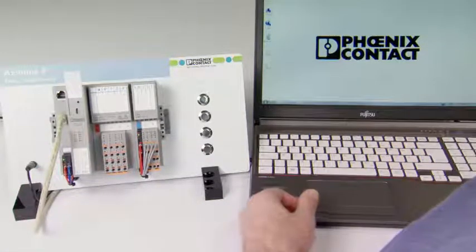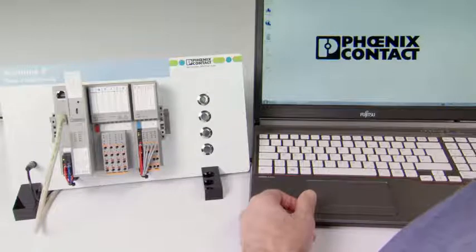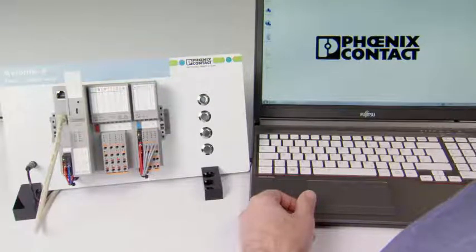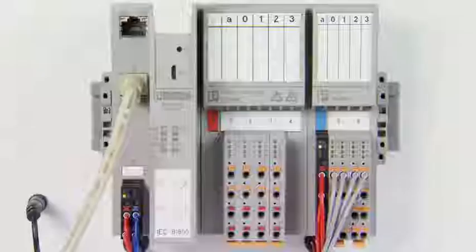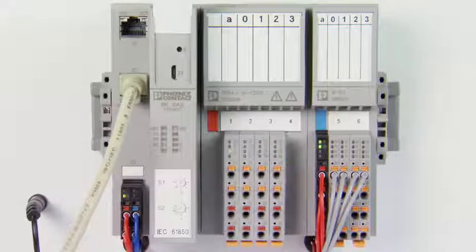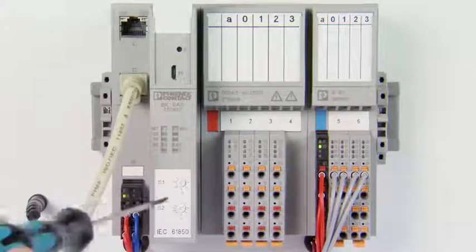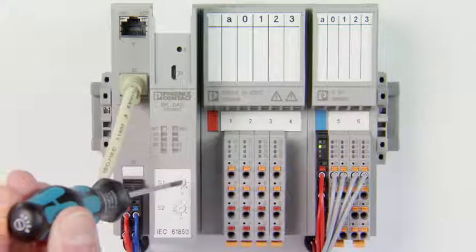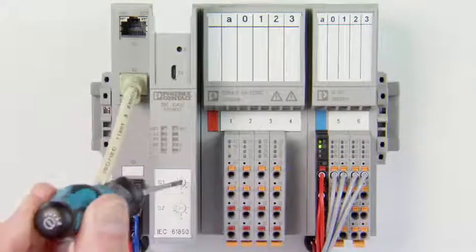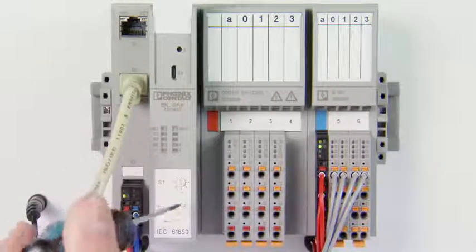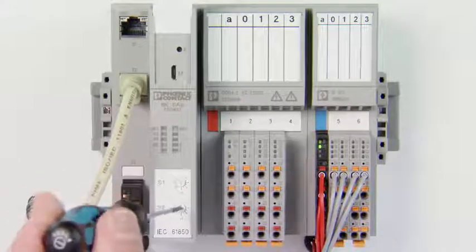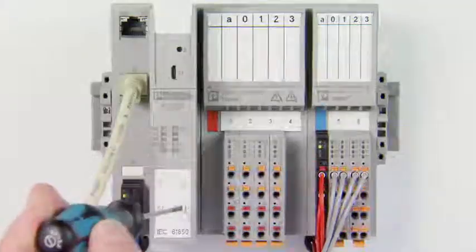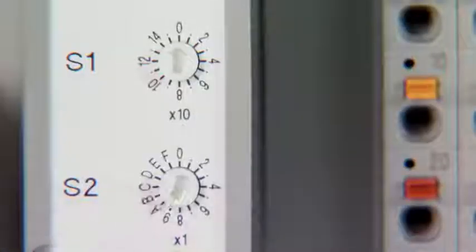To communicate with the station, the IP address is first set with the two rotary coding switches, S1 and S2, on the front side of the bus coupler. Bring the switches to positions 0 and 1 for the IP address 192.168.0.1.